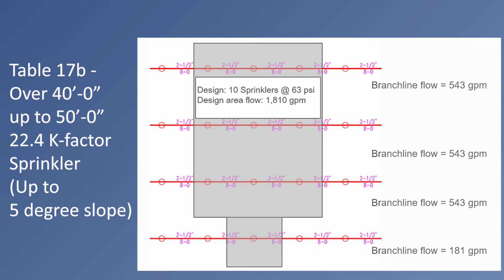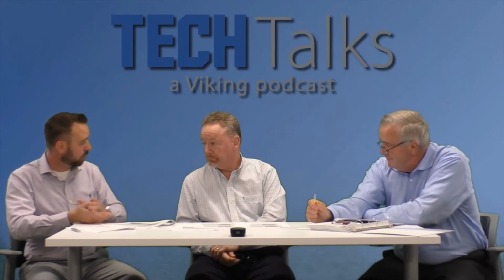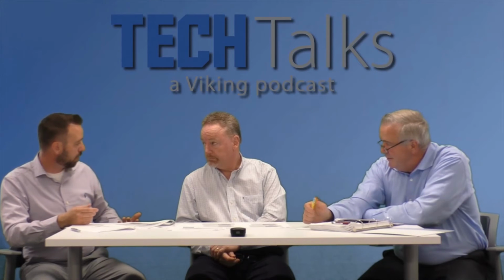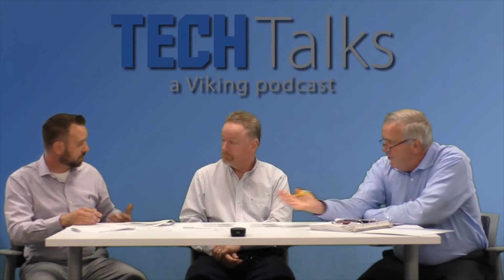Now, looking at figure 2, the branch lines were pretty close to the same, but our overall flow was significantly different. With calculating that one additional sprinkler, we're talking about large K-factor ESFR sprinklers flowing almost 200 GPM per sprinkler. So adding an additional sprinkler is pretty significant. And our overall flow came in at 1,810 GPM. So in that situation, what we were looking at is more pressure, more flow. Therefore, you're going to have larger branch lines, larger main sizes in that situation.